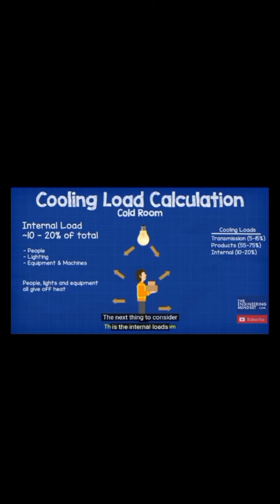The next thing to consider is the internal loads, which account for around 10 to 20%. This is the heat given off by people working in the cold room, as well as the lighting and equipment such as forklift trucks, etc. So for this, you'll need to consider what equipment will be used by the staff.